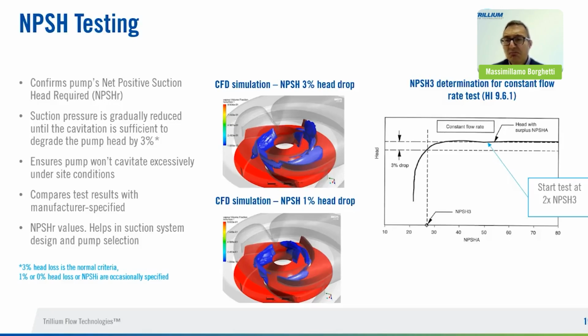3% is the generally used criteria by the industry. It is an industry standard. It is not the only one, because as you already mentioned, we can refer to 1%, that is a different quantity of bubble, or 0%, or even also to incipient cavitation, that is the condition where bubbles are almost not present. Basically, you have the vanes that are completely clean.